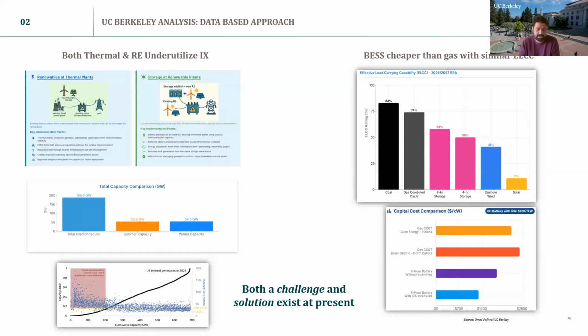So what can we do about it? While there's been a lot of effort in reforming the interconnection queue to get projects connected faster, we think there's an overlooked opportunity: the interconnection capacity of existing power plants is significantly underutilized. To give you a statistic, of the 700 gigawatts of thermal capacity in the US, 200 gigawatts operates at a capacity factor less than 15%—meaning for 85% of the time, that 200 gigawatts of interconnection capacity is essentially idle.